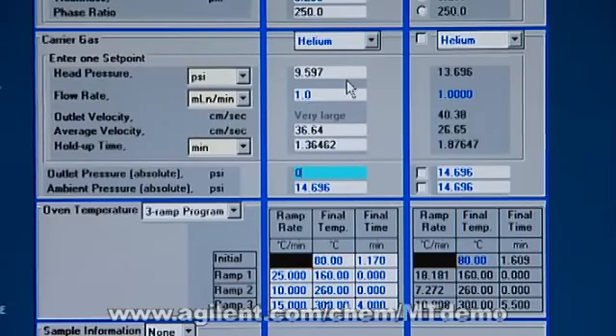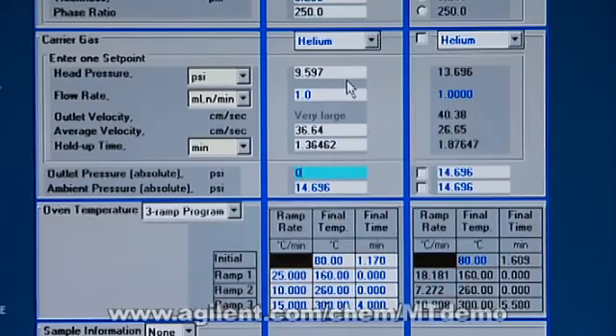Let's say I'm a guy in a mass spec lab. I've worked out my method. I've taken my helium carrier gas and my 1 milliliter per minute flow rate, and I've worked up this complicated temperature program, and I send it over to the FID guy, and he messes it up. His chromatogram looks completely different. Why? Because I forgot to tell him I have a vacuum, and if I put that in there, now I've got a different head pressure. I've got a different temperature program than he does.